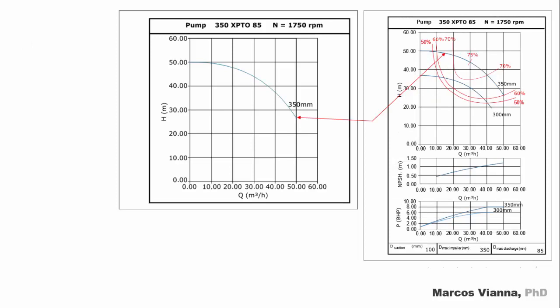Let's solve an example. This is the curve head versus flow of the 350 mm impeller. We want to find the same curve for the 300 mm impeller. This is the relationship between flow and diameter that we found. It turns to this when we put on numerical values.